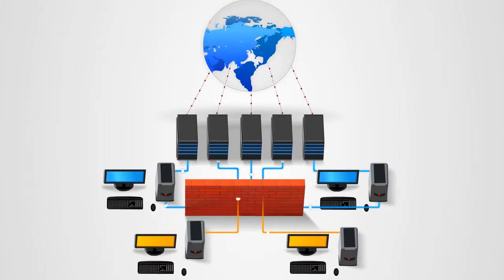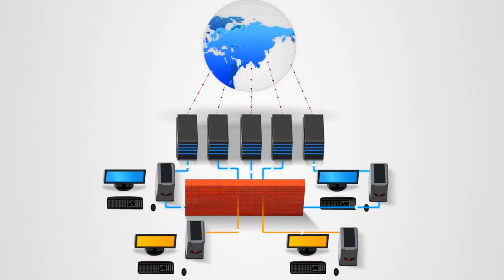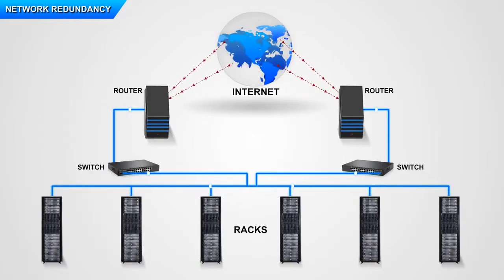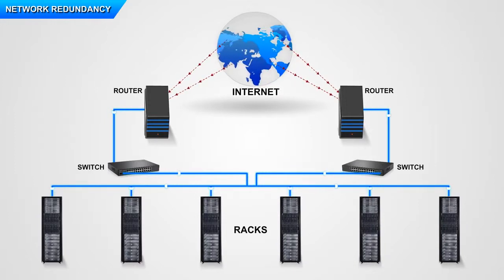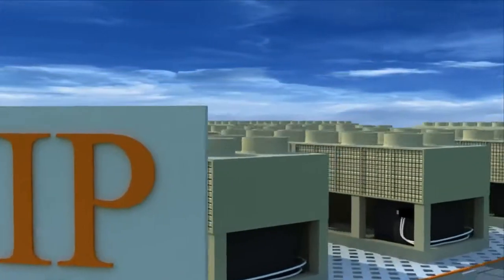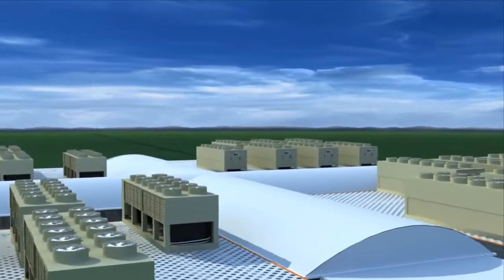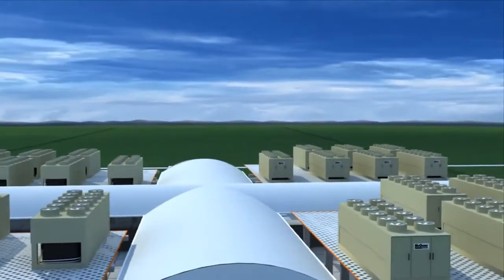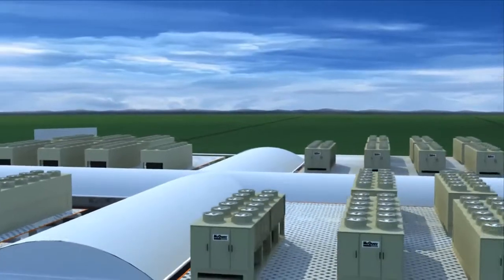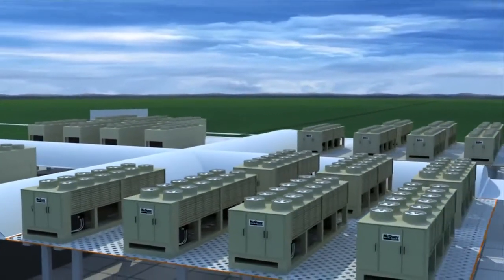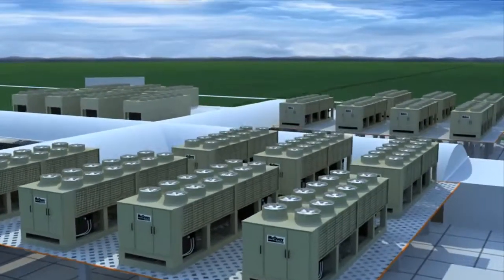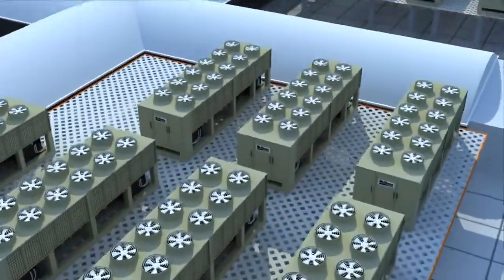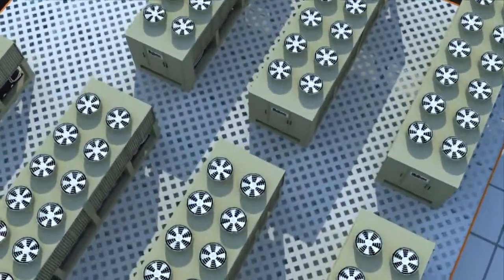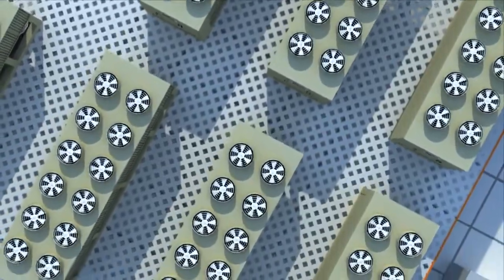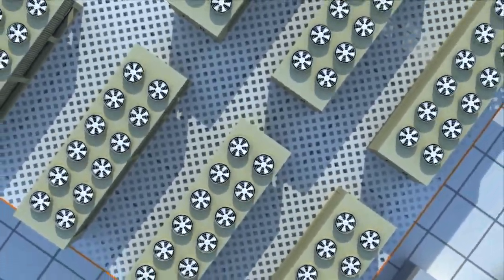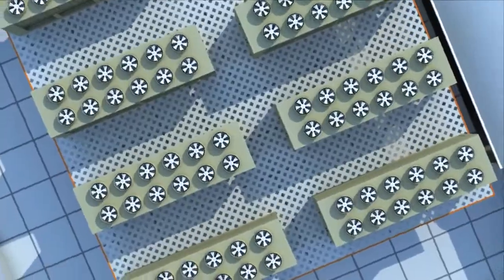Firewalls and the best security products and applications ensure the highest levels of security of data in the data center. 39 air-cooled, water-based chillers are installed on the roof of the building for cooling purposes. This gives the advantage of using any terminal equipment for precision air conditioners, in-rack solutions for high power using racks, and water cooling for large water-cooled servers. This makes the data center truly cloud-ready.